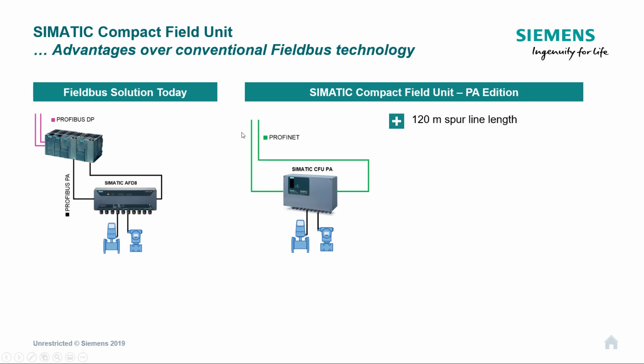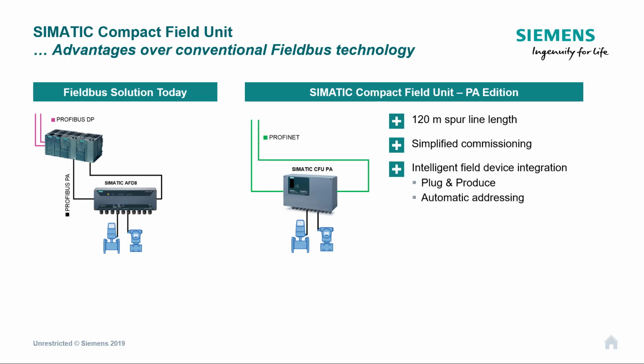So we have a look at the compact field unit. As I said, 120 meter spur lengths. We've mentioned simplified commissioning, so because it self-addresses, and anything that PDM does with the instruments is not affected by the GSD you use as well. So that's really important. So you can use the generic GSD, but you don't have to use a generic EDD for PDM or PACTware or field care, whatever you're using. You can still use the manufacturer EDD file, so you get the full functionality there.